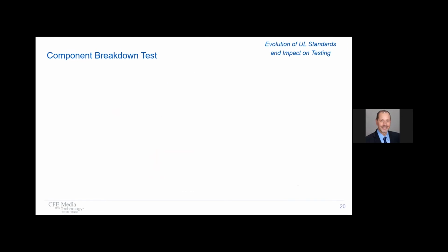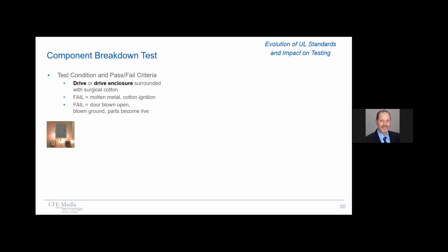Well, the test condition is such that the equipment under test must be surrounded with surgical cotton. And for a drive itself, that cotton directly surrounds the drive. But for a drive installed in a cabinet, the cotton surrounds the cabinet rather than the drive inside the cabinet.